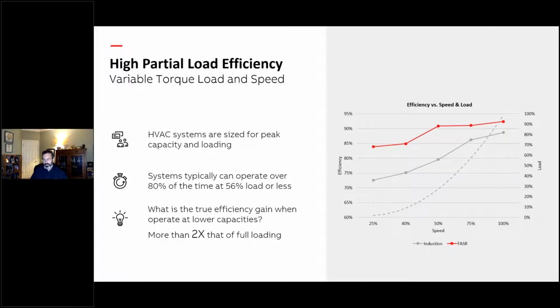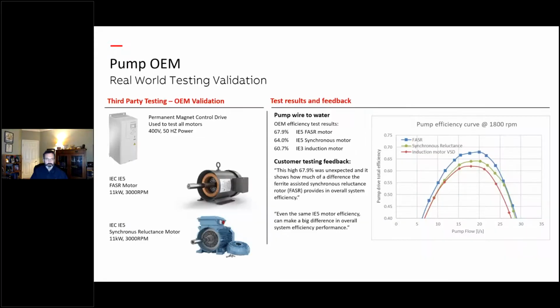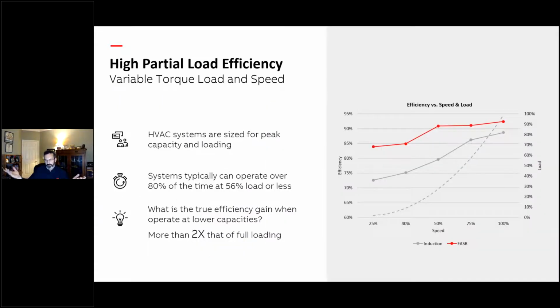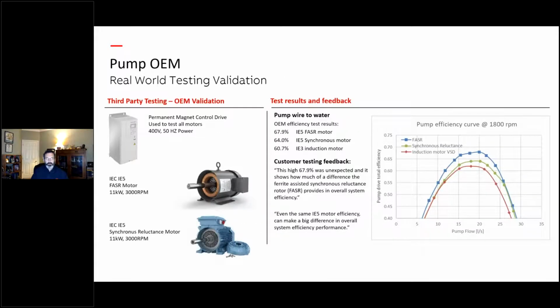So again, this was the actual lab testing data in a motor development lab. There has been customer testing on it as well. So I wanted to show you a comparison of, okay, here's lab data and here's an actual pump OEM that did testing. This pump OEM took a drive and ran it on the identical drive. They ran an induction motor. They ran an actual IE5 synchronous reluctance motor. And then they ran this IE5 ferrite assisted synchronous reluctance motor, and they ran it on their pump.